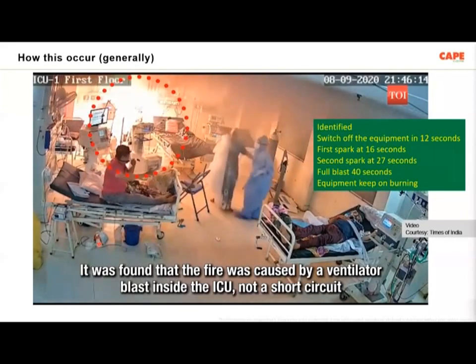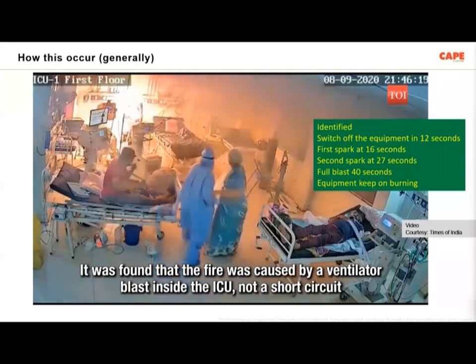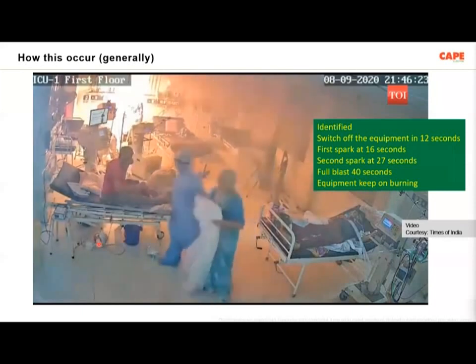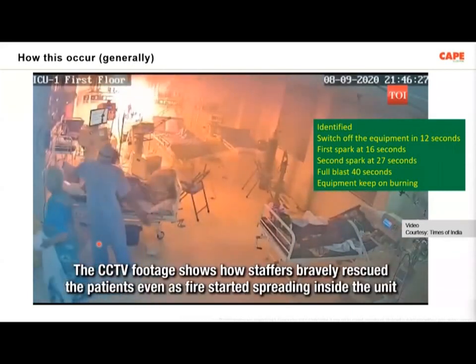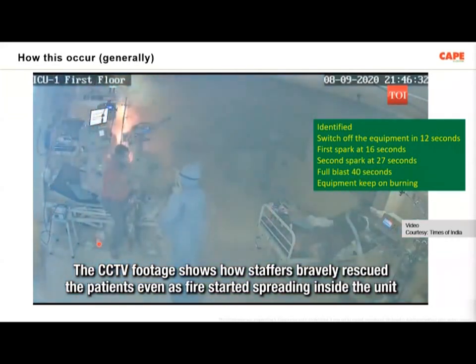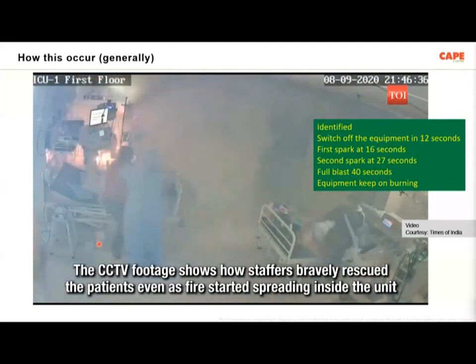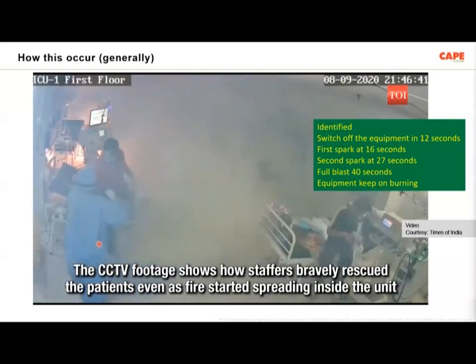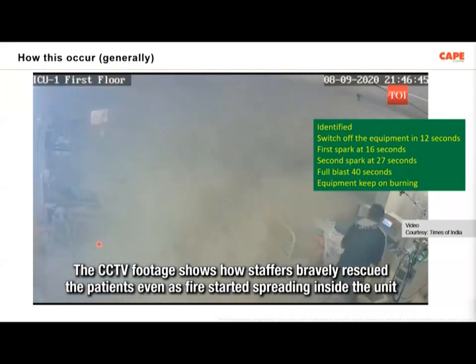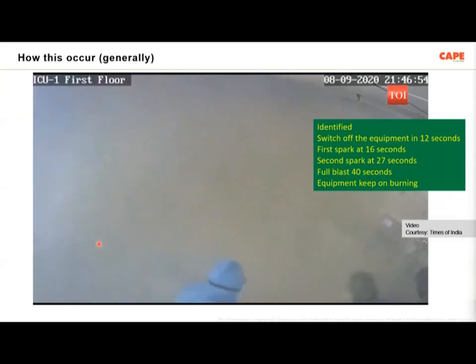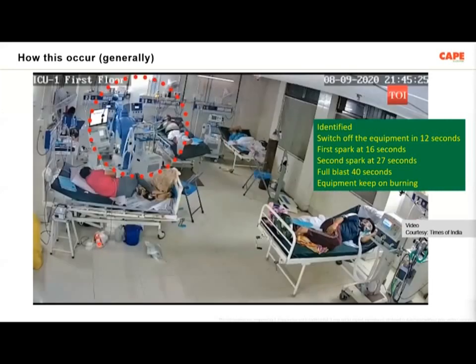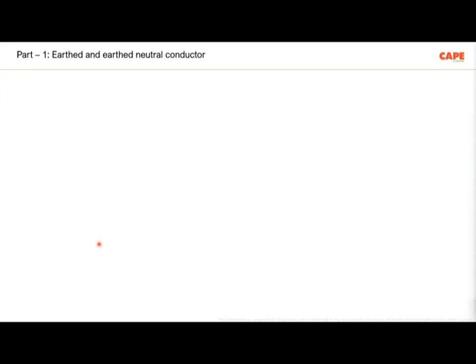Technically speaking, the electrical standards are written and followed in such a way that such electrical accidents are not supposed to happen. Number one, in this particular case, the fire started from an electrical apparatus, let us say a ventilator. Probably an air conditioner, a refrigerator, or a heater can start it. Any kind of electrical apparatus fire can start. But those product standards are made in such a way that this equipment is not supposed to produce heat or ignite a fire accident. The safety measures are made internally. In other words, electrical equipment designed and tested as per the IS standards is not supposed to create fire from electricity, or the chances are very, very small.